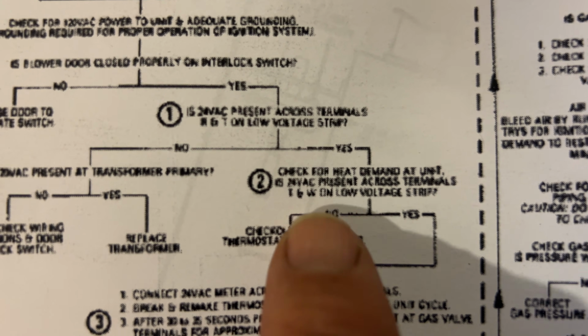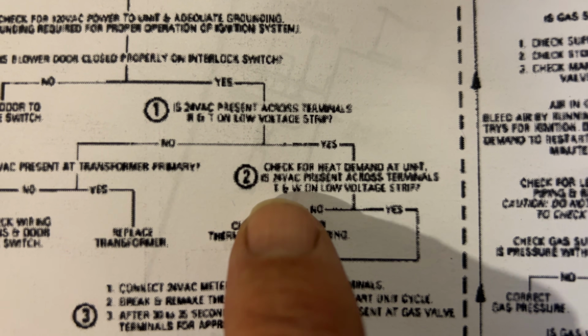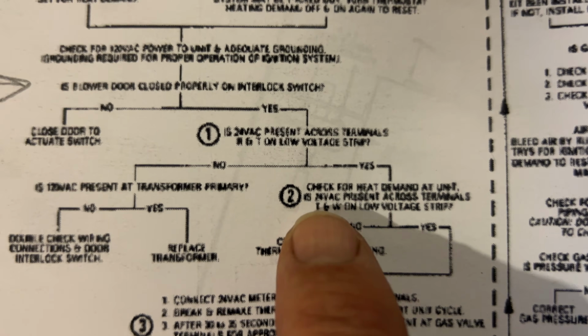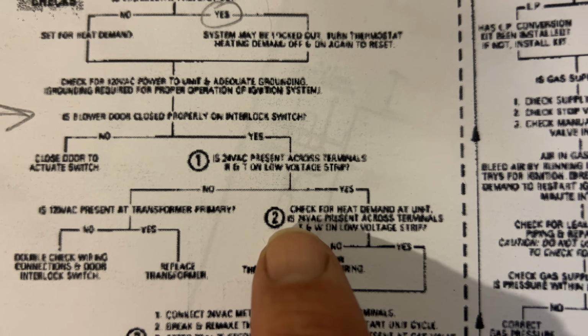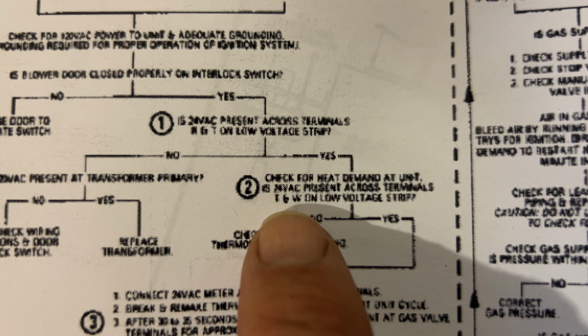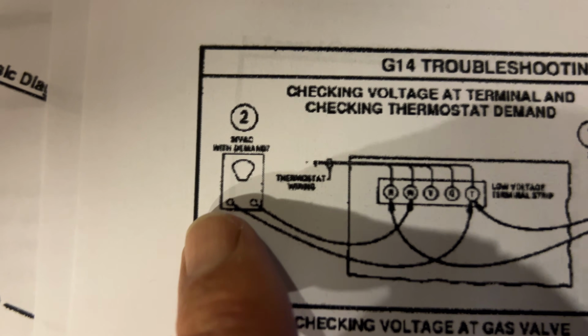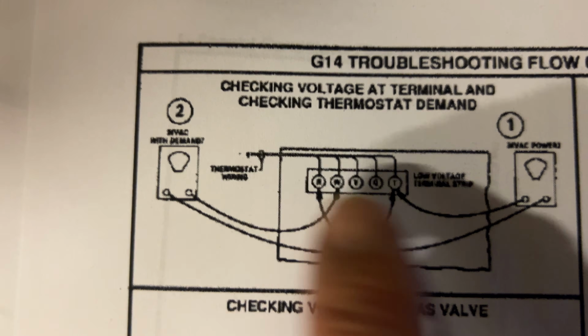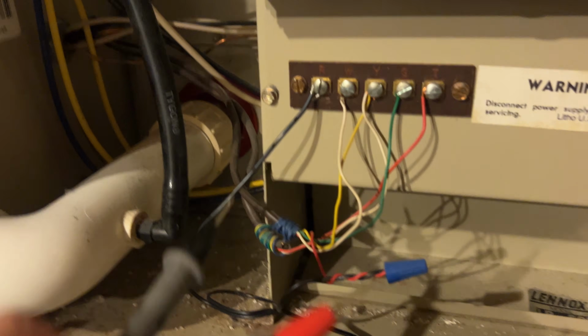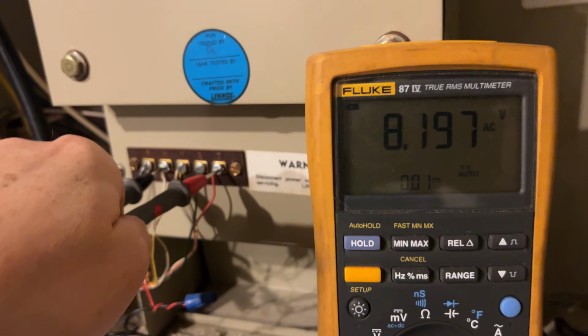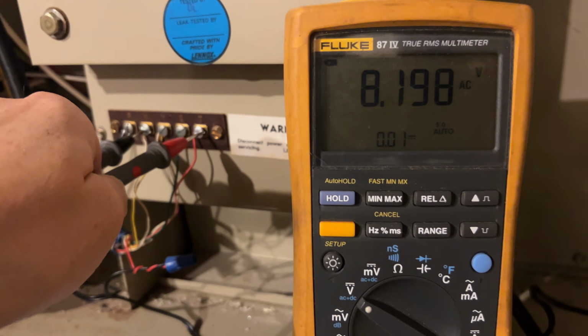We're gonna say yes on this. Now number 2, check for heat demand at the unit. That's gonna tell us whether or not our thermostat is calling for the correct heat. Check T and W, no, that's number 2. Really hard to read this flow chart, but luckily these numbers on the following page give us a clearer picture of what to do. So we've got to go from here to T. Let's do that. We've got 8.2 volts, 8 volts right there.